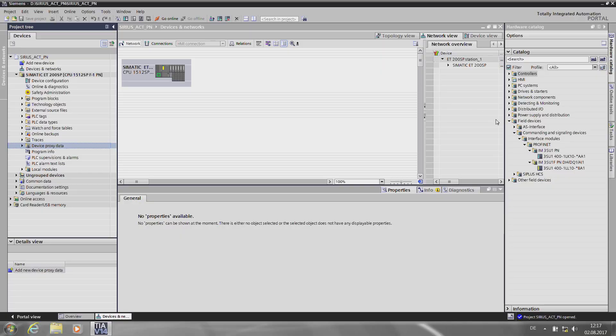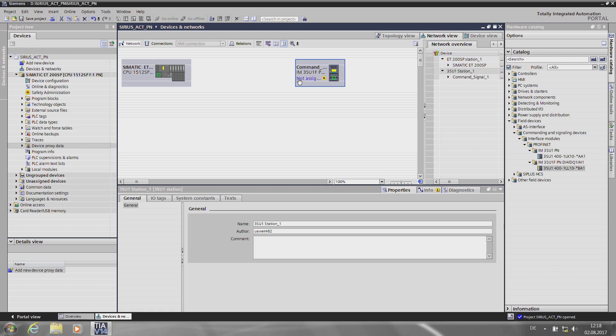That's what I want to show you now. We are currently in the network view in the TIA Portal. Now, we have to select our interface module for Sirius Act with PROFINET from the hardware catalog. I can either do it via the tree structure or enter the MLFB at the top. The Failsafe interface module is moved into the network view by drag and drop. Our interface module is then connected to the controller. This is also done by drag and drop.